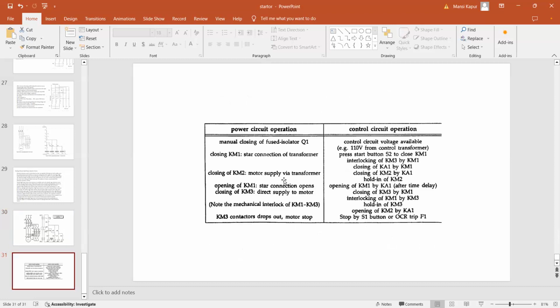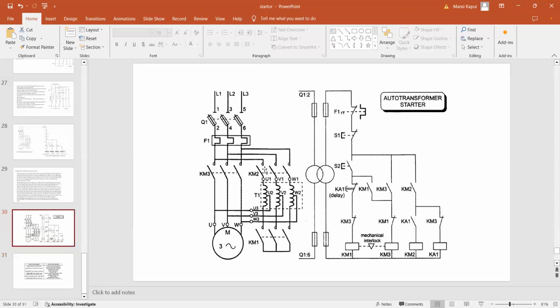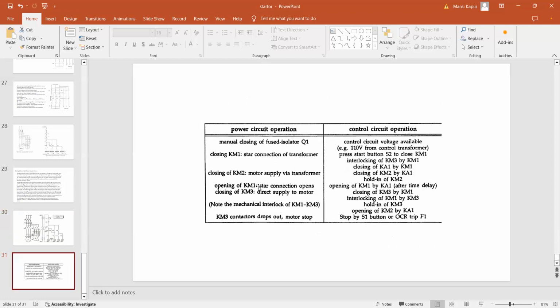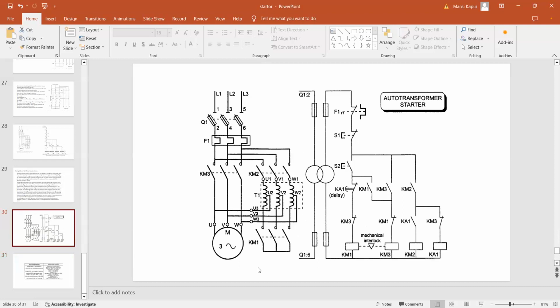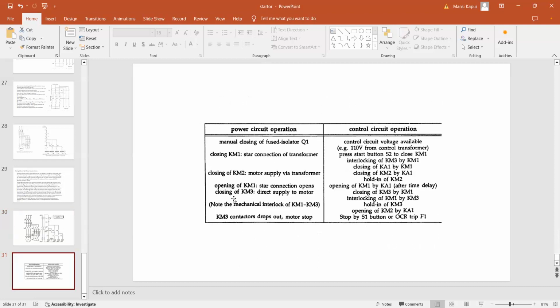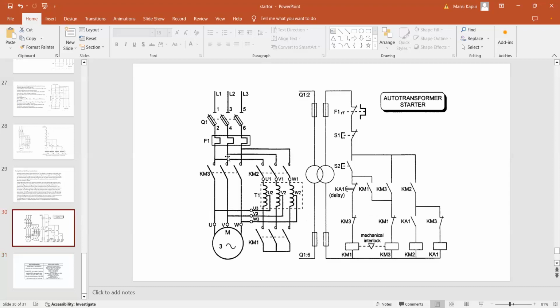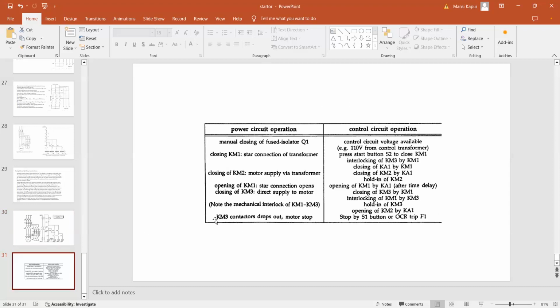Closing of KM2 gives motor supply via the transformer. When KM2 is closed, these are the tappings and the motor is getting supplied. Opening of KM1 means the star connection opens. Closing of KM3 gives direct supply to the motor, this is in the power circuit.